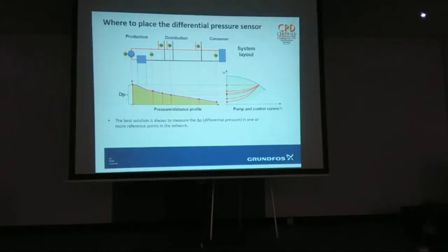The bigger the speed reduction, the greater the energy saving. But you've got to make sure the sub-circuits don't drop below their required pressure. Because if it drops below what they need, that's not the index circuit; maybe that one is. Or you can put different sensors on multiple buildings and feed it back to the BMS, and then they go, oh hang on, that one's a bit light. Raise it. Pump duty: the selection of the pump is still the same duty, 250 kPa and 50 litres a second, but how it controls depends on where and what you're doing with the sensors.